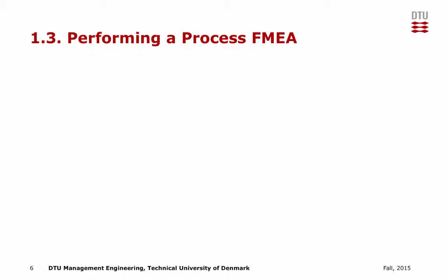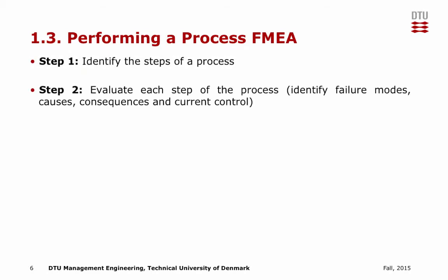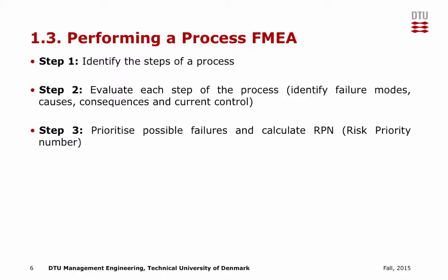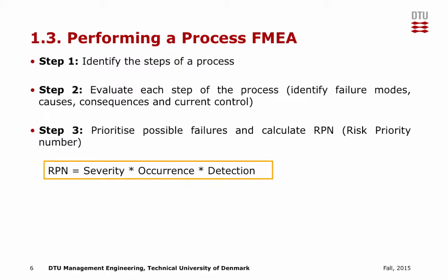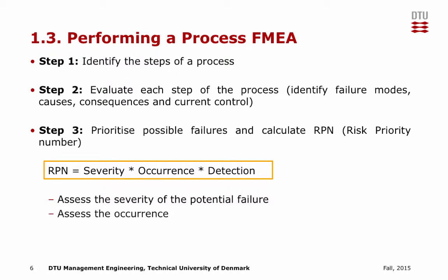Performing a process FMEA can be divided into five steps. Step 1: each step in the process is identified. Step 2: these steps are evaluated based on failure mode, causes, consequences, and current controls. Step 3: the possible failures are prioritized and the Risk Priority Number, also known as RPN, is calculated. The RPN is based on three factors: severity, occurrence, and detection — that is, how severe the problem is, how frequently the failure occurs, and how easy the failure is to detect.